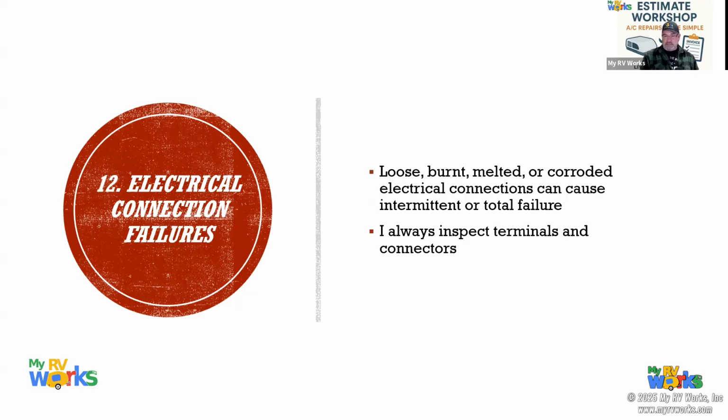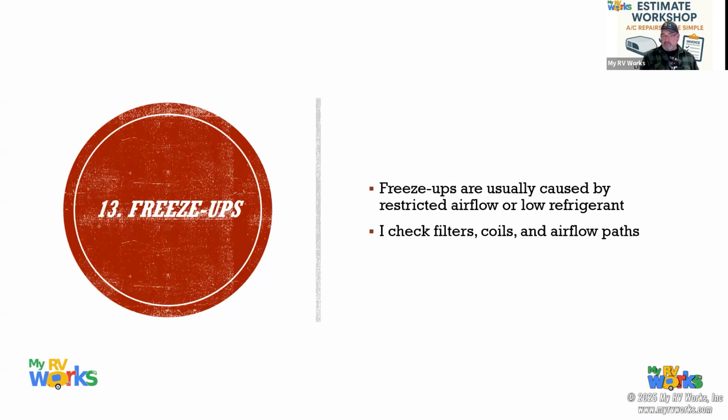And then electrical connections, you might have loose, burnt, melted, corroded electrical terminals. I got some great pictures of all that kind of stuff. And then the last one's freeze ups. And I have another slide. We're going to go a little bit deeper into freeze ups, what would cause a freeze up and how to address those things.